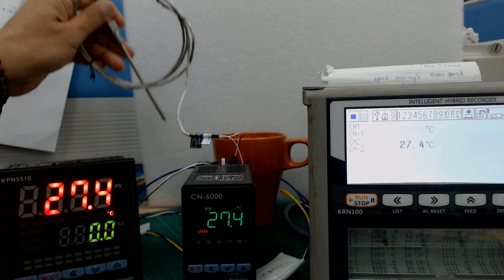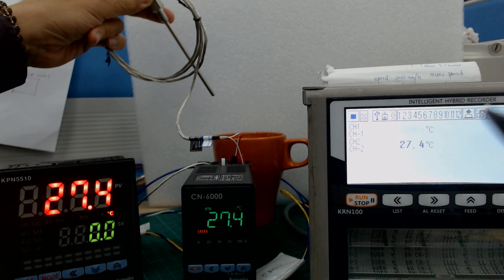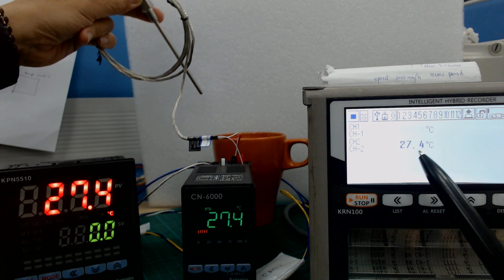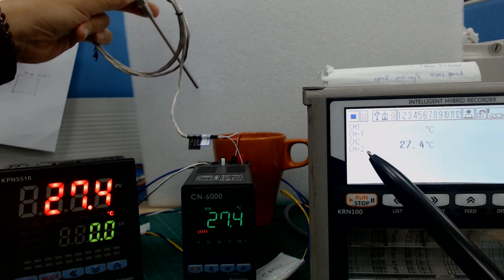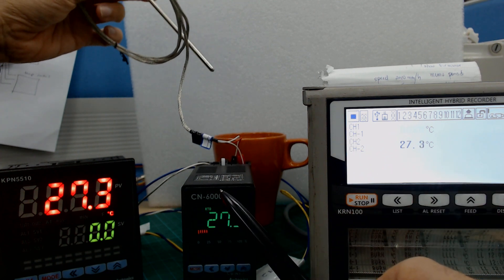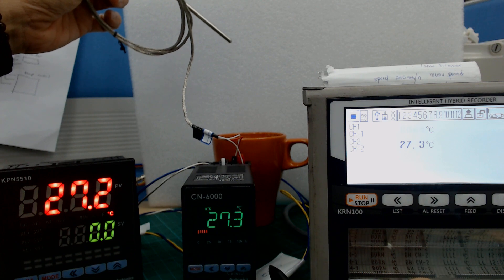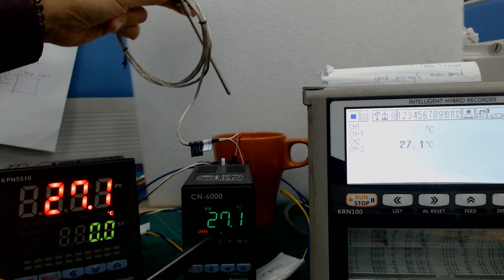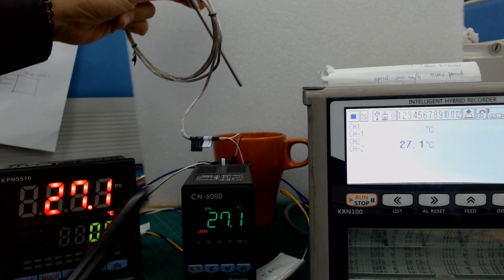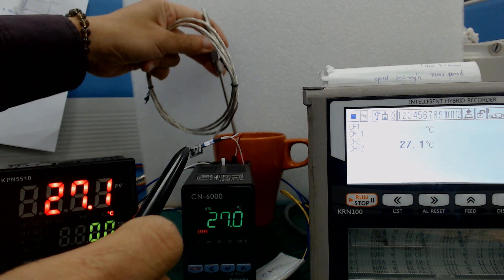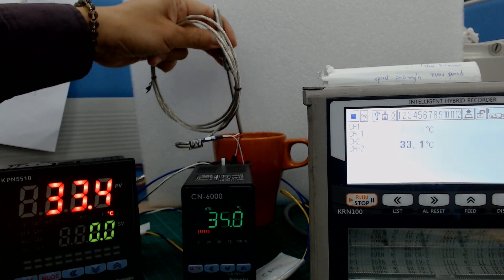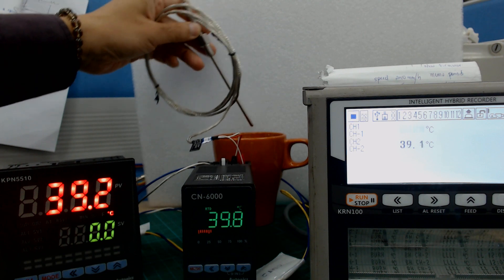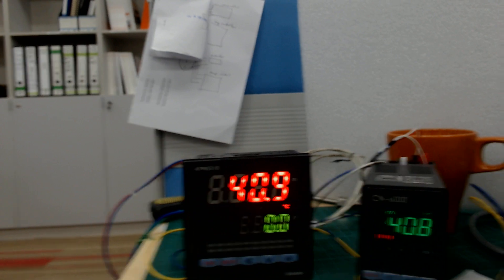Okay, this is the PT100 probe in my left hand. You can see the KRN 100, the temperature 27.4. I use channel 2 signal 4 to 20mA input. This is the converter CN6000, input PT100, and then goes to output two and output one to this KPN, output two to this recorder. You can see the temperature 27.1. This is the main converter. I'll dip it into hot water so it will rise up.